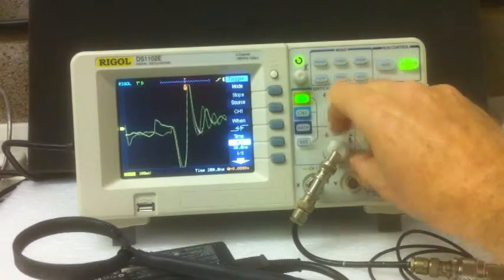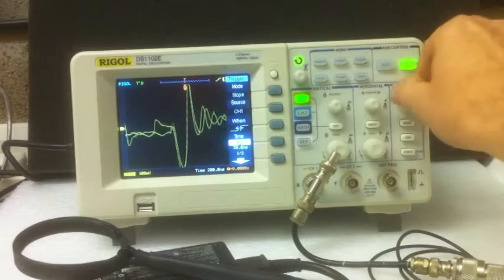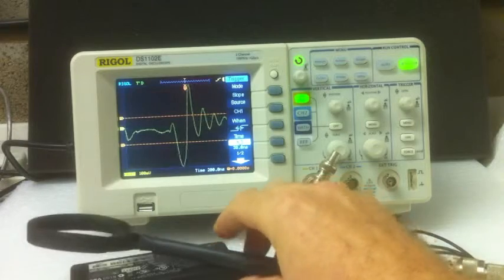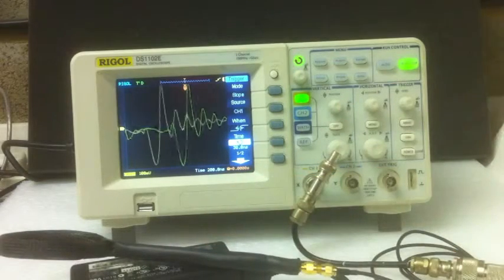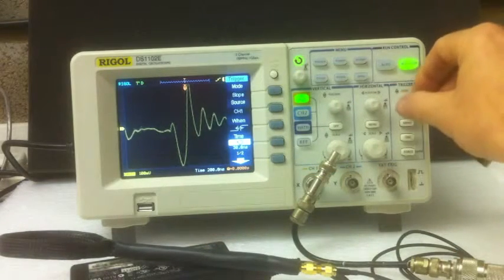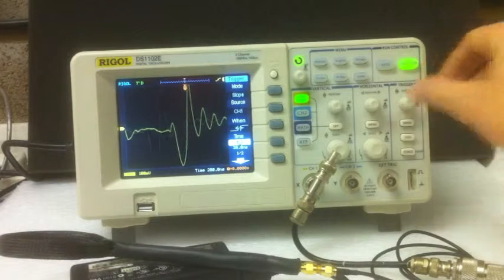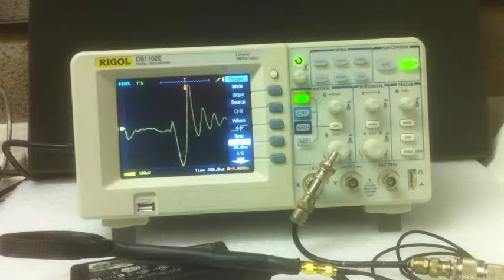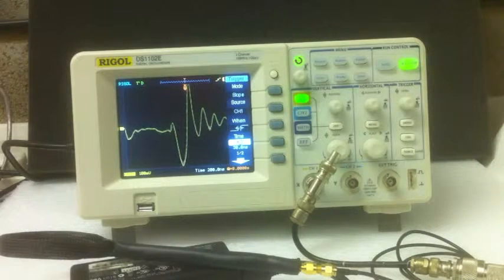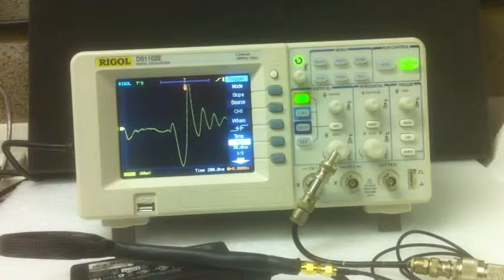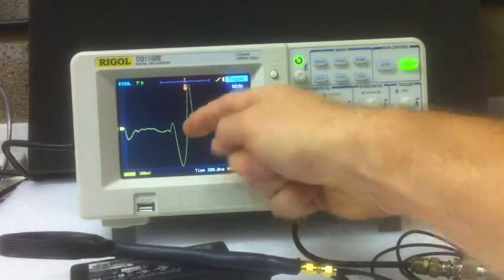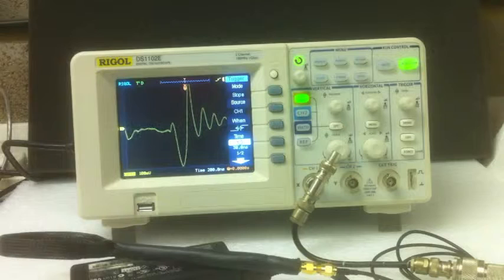And in fact, if I wind up the volume a little bit, I can see exactly what's happening with that signal. So let's just show you just how good that can be. That's a really very stable trigger now on that signal. You can investigate just one zero crossing. So I've tuned in the trigger simply to display just one zero crossing, which is this very fast central one.